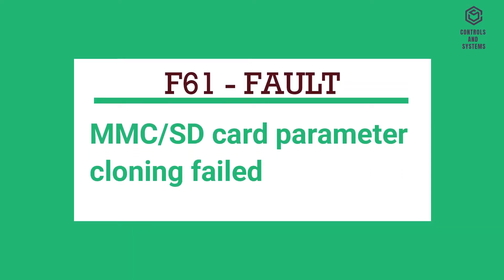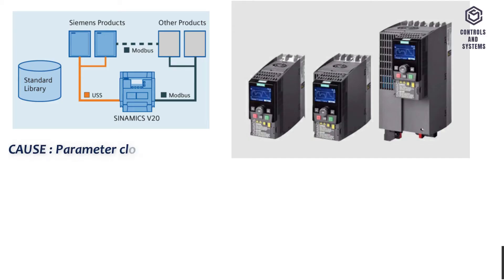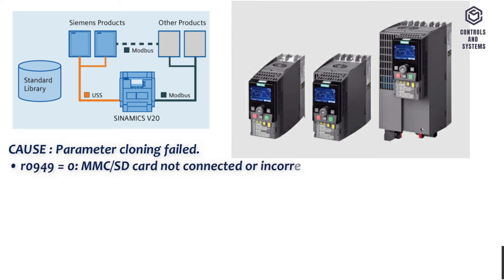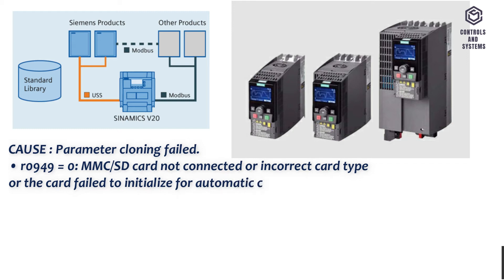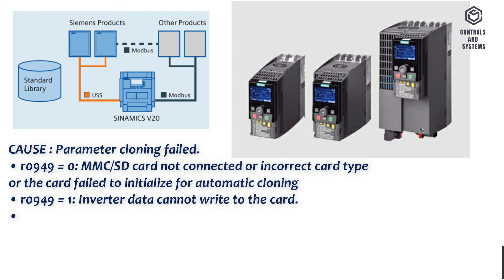F61 Fault: MMC/SD card parameter cloning failed. Cause: Parameter cloning failed. R0949 equals 0: MMC/SD card not connected, incorrect card type, or the card failed to initialize for automatic cloning. R0949 equals 1: inverter data cannot be written to the card. R0949 equals 2: parameter cloning file not available.